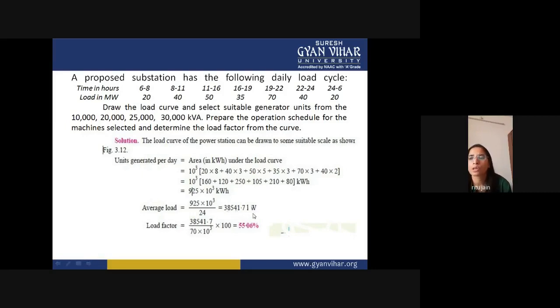So the average load of this substation is 38,541.71 kilowatt, which is divided by your maximum demand, which is your 70 megawatt. So you can easily calculate the load factor, which is 55.06%.